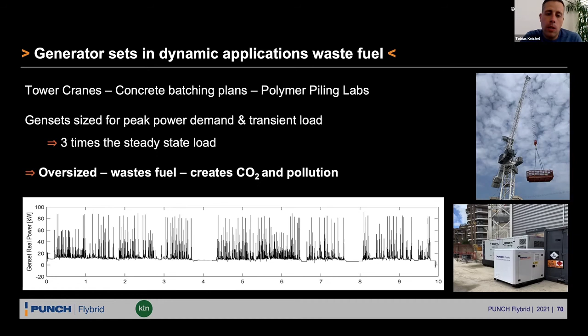If you need to use a generator to power this tower crane, you have to size it for the peak power demand and the transient load. That means you have to size it 3 times bigger than the steady state load, and you end up running an oversized powertrain that wastes fuel and creates unnecessary CO2 and pollution.